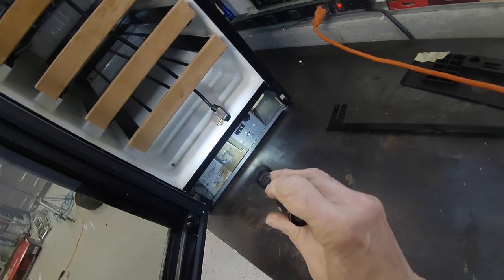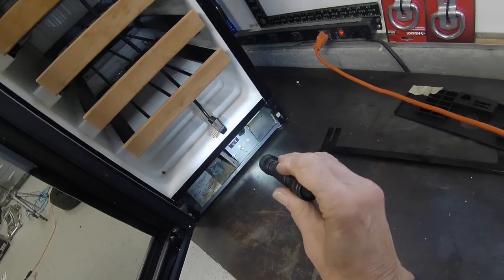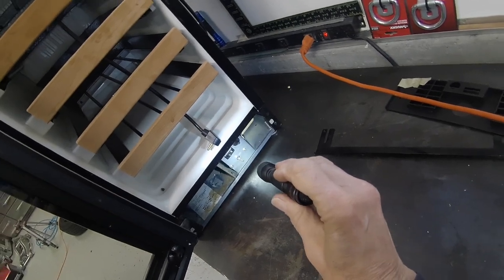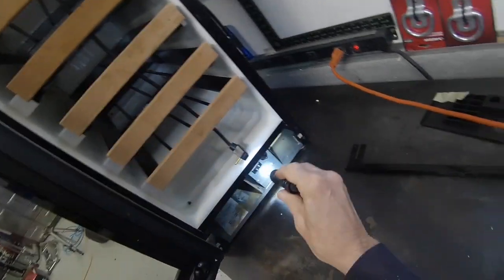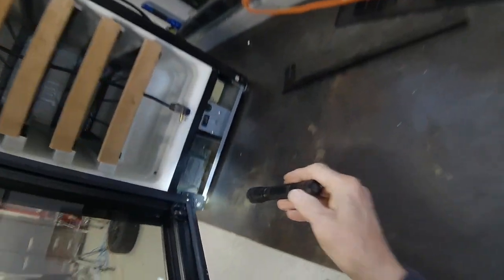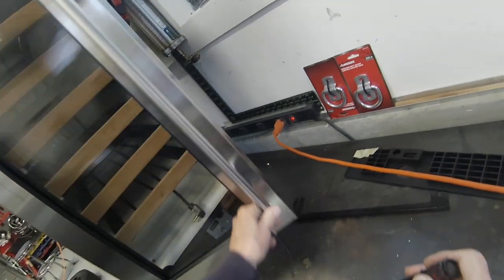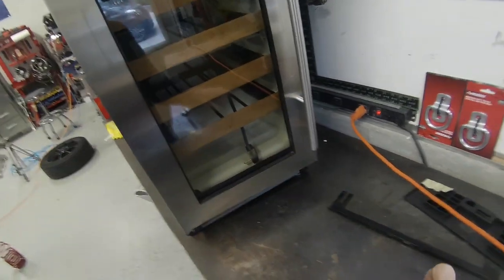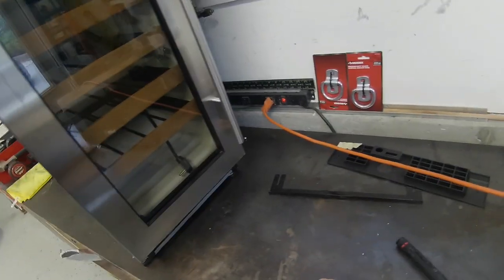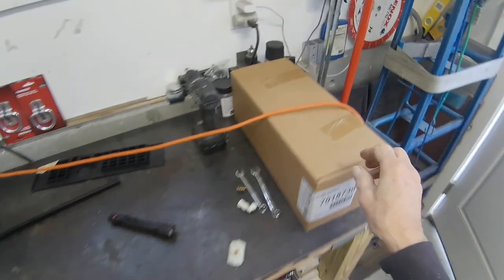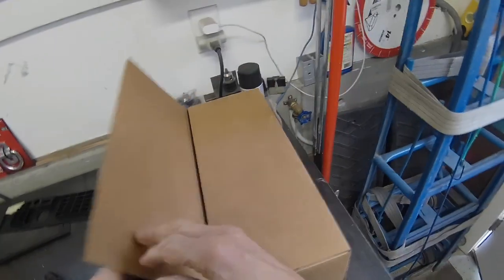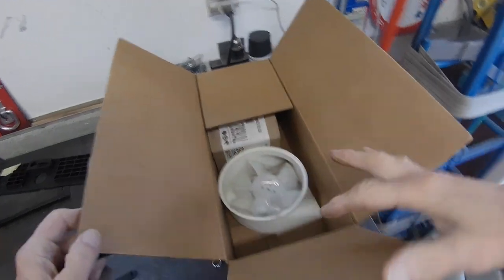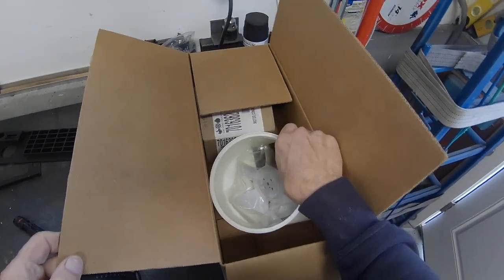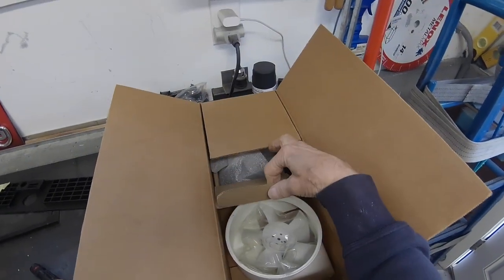It's a common problem on this model. Other than the thermostats going bad, when the condenser gets really dirty, which is down there and which we've cleaned, the condenser fan motor goes bad and gets so hot under there it melts the shroud. So we have a new shroud kit here, with the fan blade and a new condenser fan motor.